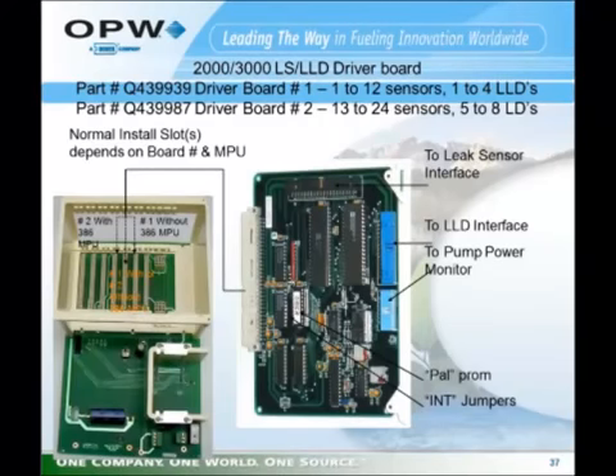The leak sensor line leak detector driver board. The system will support up to 2 of these boards. When used for a leak sensor driver, each board will support up to 12 sensors. Driver board number 1 would be sensor 1 through 12. Driver board number 2 would be sensor 13 through 24. When used for line leak detection, board number 1 is line 1 through 4. Board number 2 is line 5 through 8.